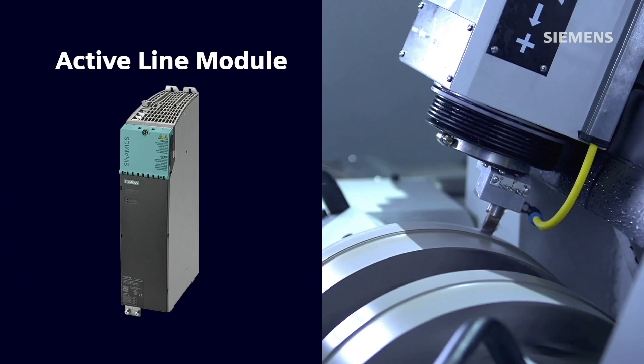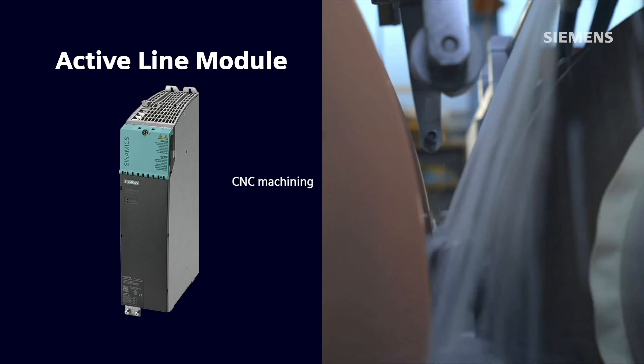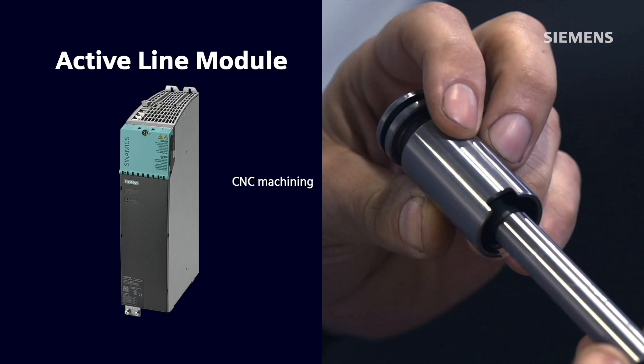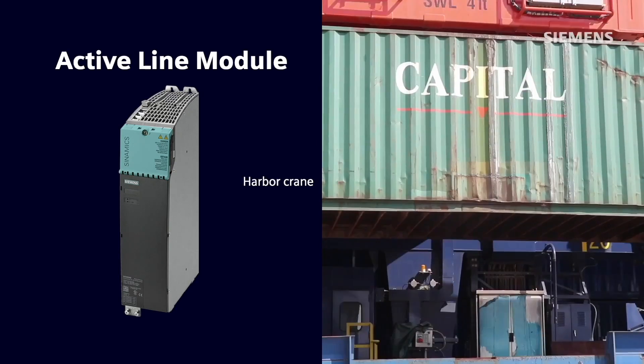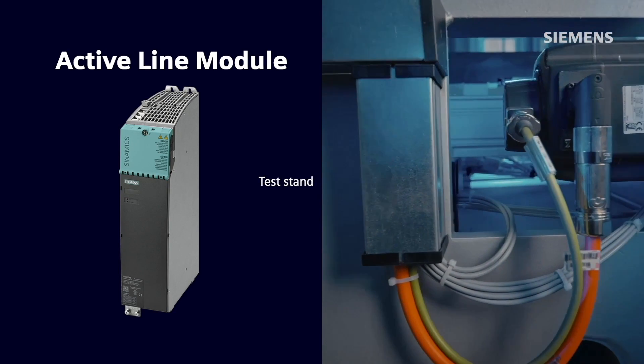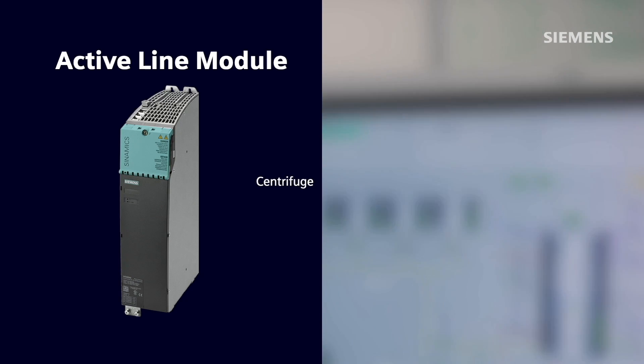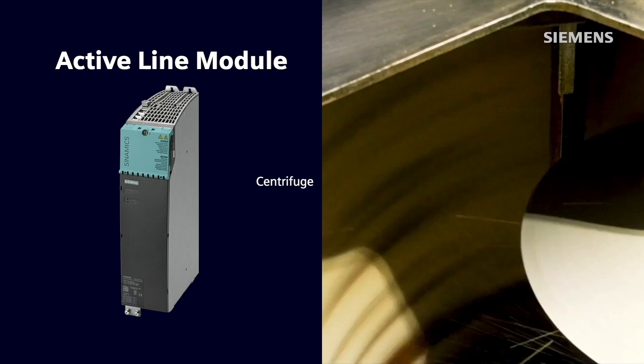For high performance applications, such as CNC machine tooling, where we want to try to remove any type of disturbances out of the system in order to achieve the smoothest finish and highest tolerance cut, it is typical to use the active line module to achieve this. The active line module would also be a primary choice for applications such as a harbor crane, where there would be considerable amount of regenerating. Applications such as test stands, or even a single axis application such as a centrifuge, would also benefit from having large regeneration cycles that have the requirement to feed back very clean power.